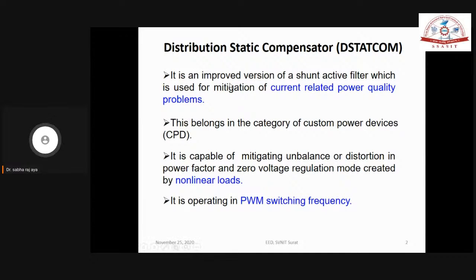Okay, so the meaning is that this whole device is going to work in 2 modes: one is the PFC mode and the other is the ZVR mode. Means we have an additional feature here. This STATCOM is going to work for 4 functions if we have a 4-wire system, additionally with voltage regulation. Means we are going to achieve the voltage level near the rated value. But still we have some problem.